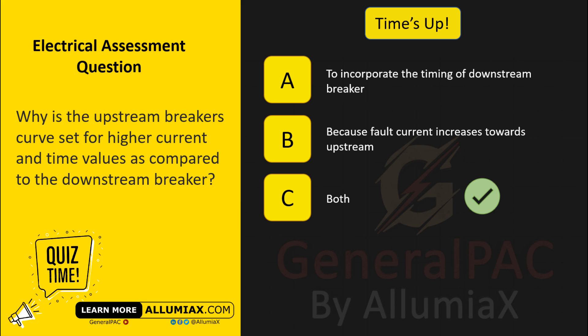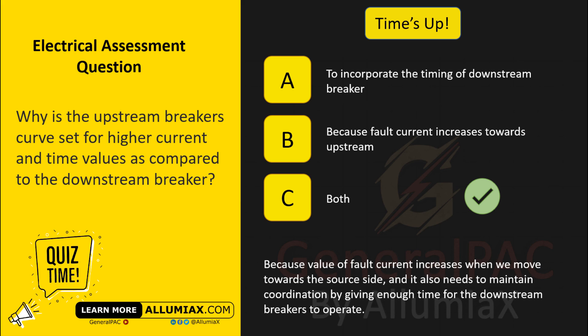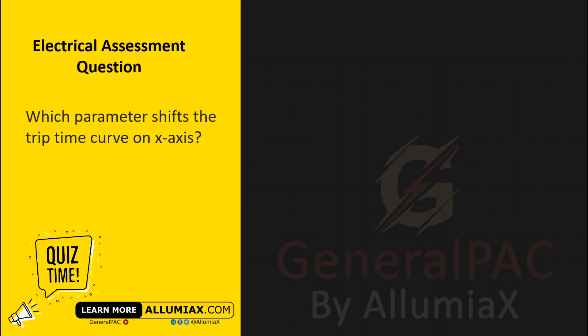The answer is C — both. Because the value of fault current increases when we move towards the source side, and it also needs to maintain coordination by giving enough time for the downstream breaker to operate. Which parameter shifts the trip time curve on the X axis?